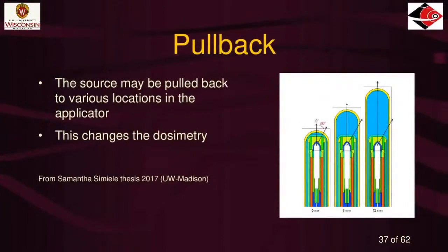In addition to the applicator type, former UW graduate Samantha Simile did her PhD on the Xoft Axxent source inside cervical applicators using Monte Carlo models. Her models show different amounts of pullback — if you step a Xoft source back through its applicator, each one of those dwell positions has a different set of dosimetry parameters. The change is not huge but enough that you need to take it into account. This is one more challenge in EBT dosimetry.